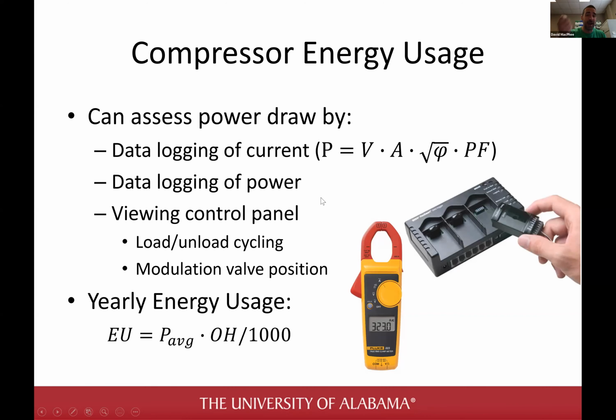So you can get the power drawn by the compressor. Best case scenario, you log the power for an entire year to find out how much it's drawing. You can do that with the current transducer, or you can actually log power directly, but that needs a power quality meter, which is expensive and too complicated, so unless you're really into power logging, I'd say don't bother with that.